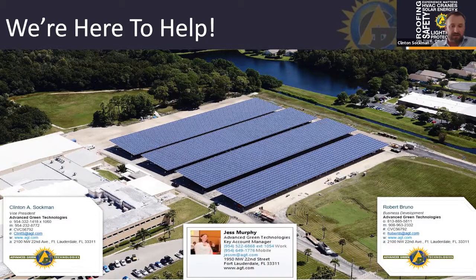That's us coming out to check your fuses, check your filters, check for corrosion, loose connections, make sure we don't have anything that's gotten less structurally sound over time. That's a once a year scheduled maintenance. Other than that, we recommend remote monitoring through our data system, so you can see if you have a production loss that's not explained by the current weather. So once a year is recommended.